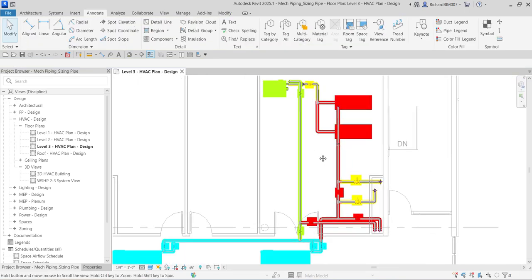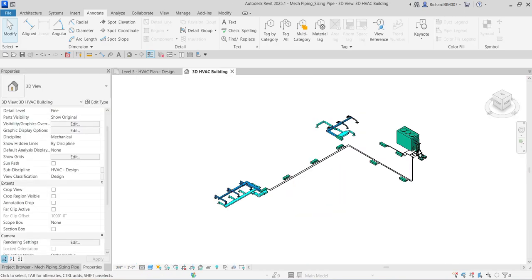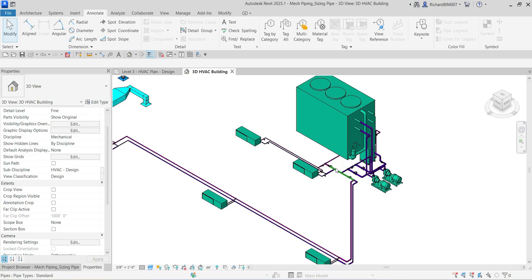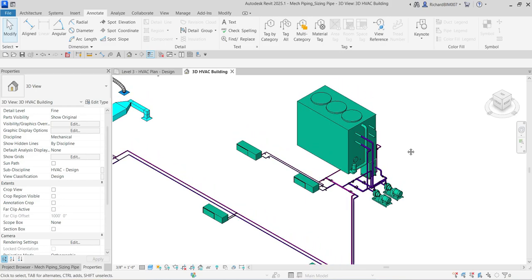After sizing the piping, let's inspect the system. We'll use the System Inspector to inspect the Level 3 hydronic piping system. The System Inspector lets you inspect each piping system for flow, pressure, and pressure loss by placing the cursor over a pipe or mechanical equipment. It helps you quickly detect problem areas in your design and resolve them immediately.